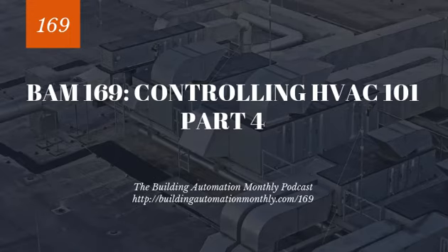which is good, because we will typically use heat exchangers in order to transfer heat from a steam loop into a hot water loop. So typically you'll have a steam loop that runs around the campus, and you'll have these heat exchangers that sit in the building, and they allow you to transfer heat from the steam side to the hot water side, and that then acts as your quote hot water boiler for that building.